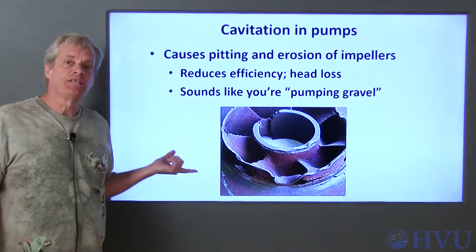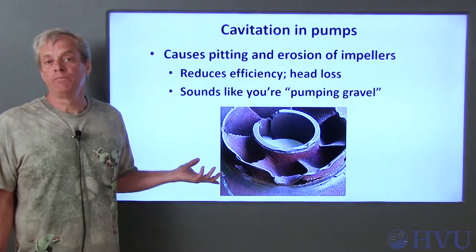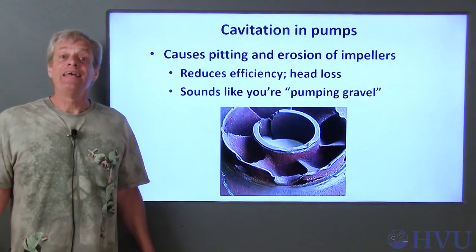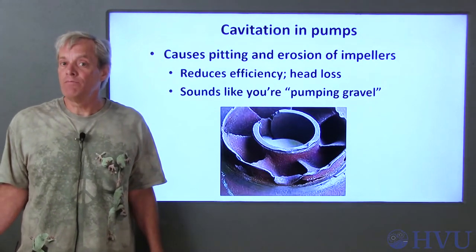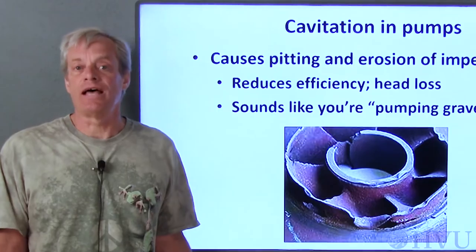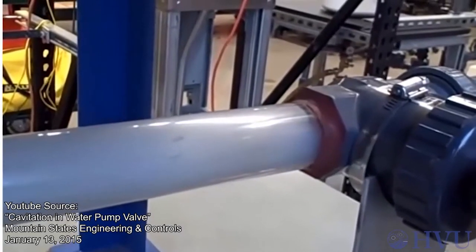Even if the cavitation doesn't damage the pump, it invariably causes reduced performance and it can create vibration issues. Cavitation sounds like the pump is pumping gravel.